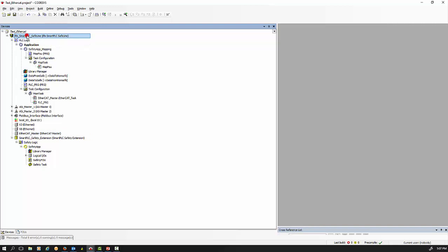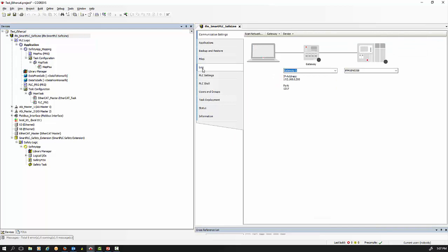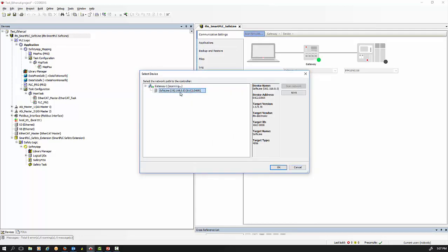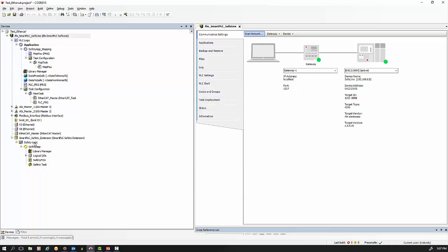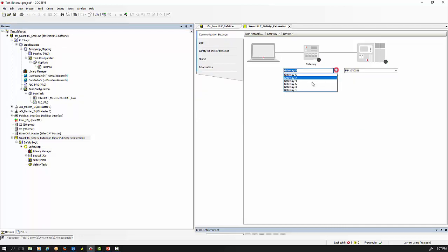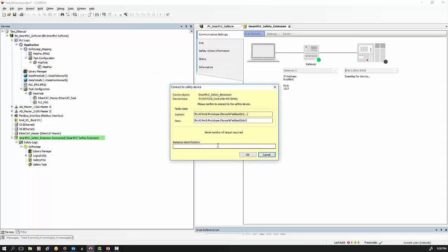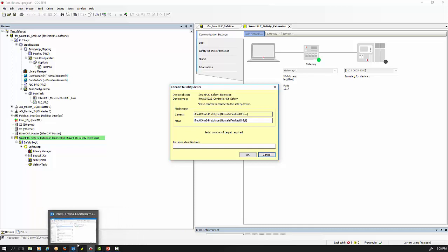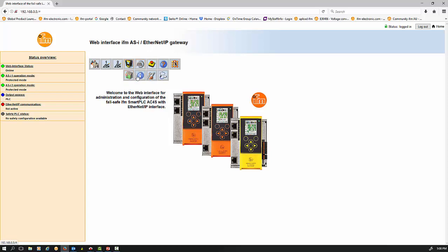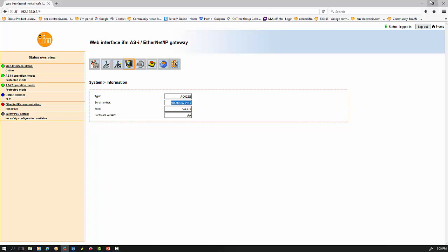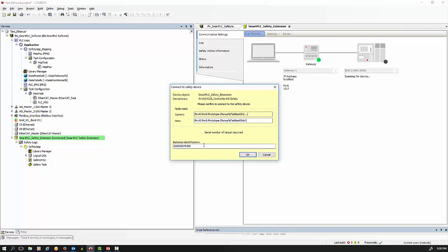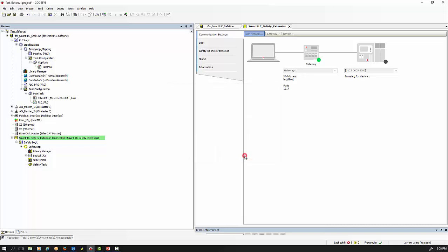You'll have to be online with the PLC, so double-click on your top device and go online with the non-safe PLC. We scan and find our safety PLC — it's a SafeLine, but I'm connecting to the non-safe side. I also need to do the same for my safety PLC. Once you get online with your safety PLC, it'll ask you to insert the serial number to verify the safety PLC and confirm the device is licensed with CODESYS. An easy way is to go to the web interface, go to your PLC icon information, and just copy-paste it.